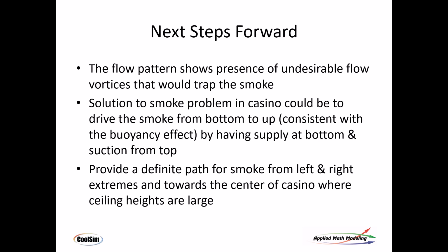everything up at the ceiling into returns, and so we essentially built a bottom to top kind of airflow where all of the air would go up and out. No supplies at the top, and that was part of the problem they had in this design.